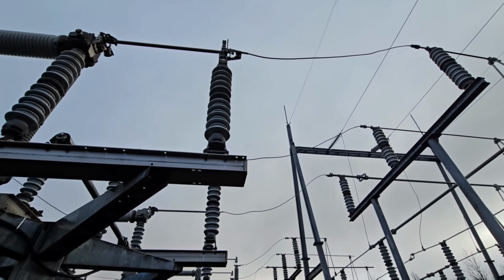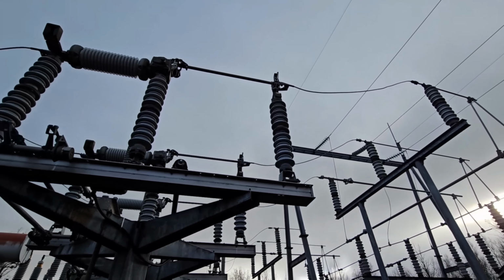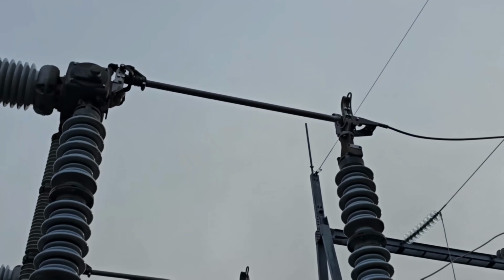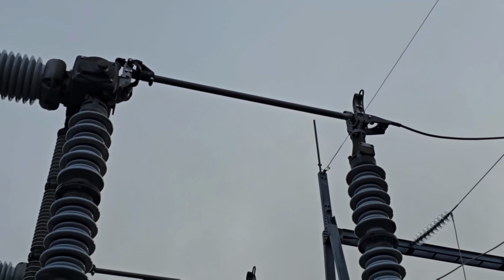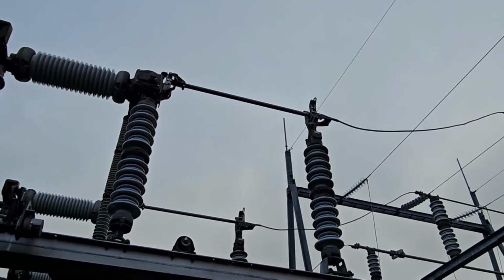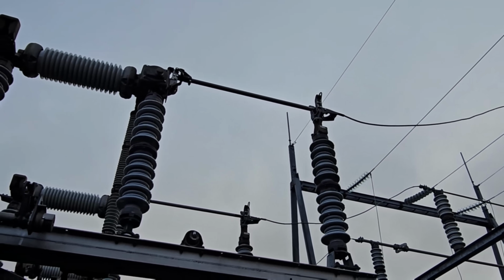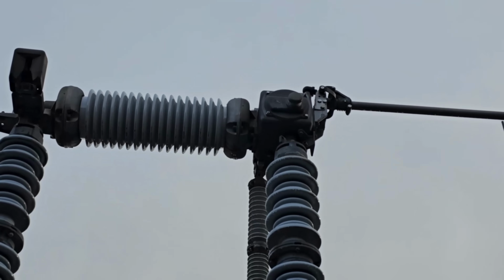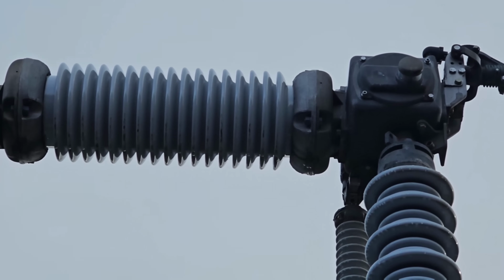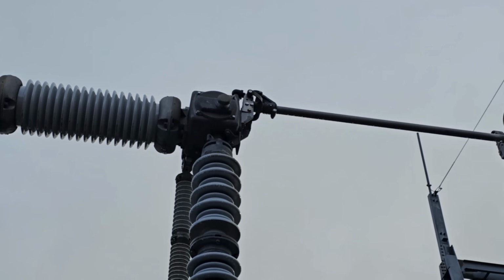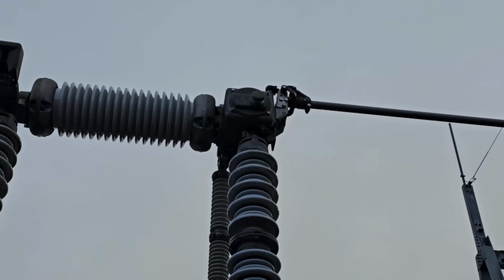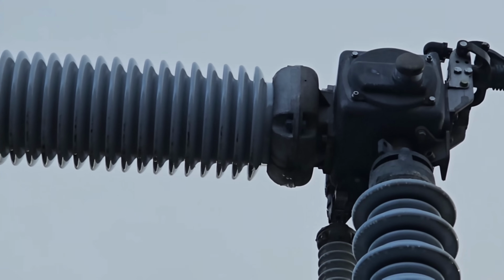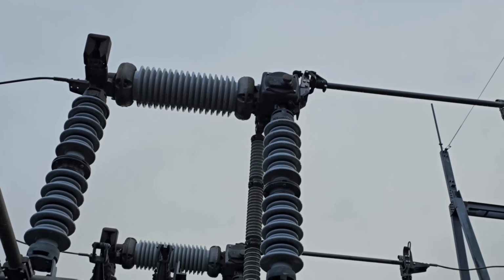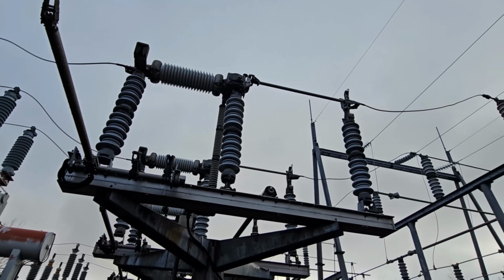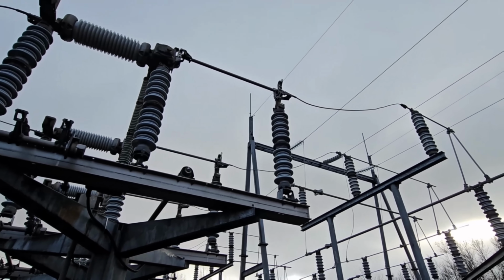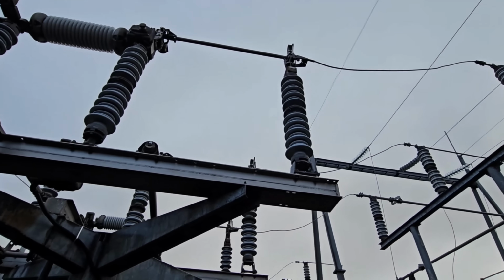This is the unit that was out in the woods when I had to walk in through that trail. That massive bar right there opens up to disconnect power. Even if power shut off, it isolates that line so that it's not connected to our system. This big tank right here is filled with sulfur hexafluoride gas. So when that switch is opened, there's an actual connection inside that unit. The sulfur hexafluoride gas snuffs out any arcing from any residual power that's on the line. So we disconnected both of those.